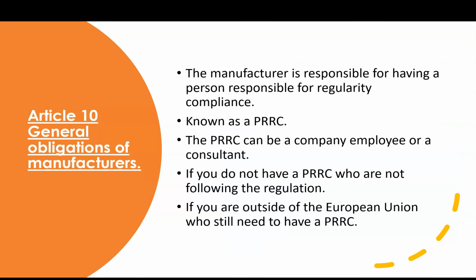The manufacturer is responsible for having a person responsible for regulatory compliance. For short, this person is known as a PRRC. The PRRC can be a company employee or a consultant. If you do not have a dedicated PRRC, you are not following the In Vitro Diagnostic Medical Device Regulation 2017-746. If you are a manufacturer outside the European Union, you will need to have a PRRC.